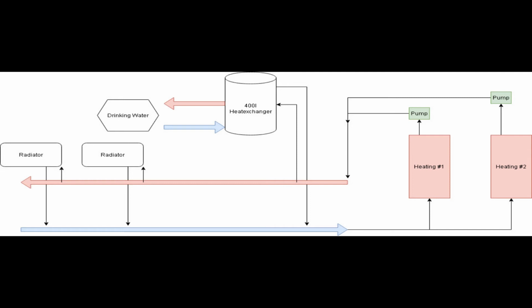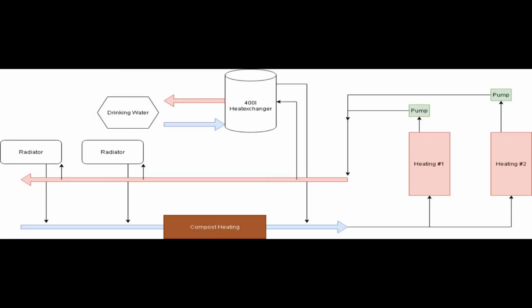The two main heat sources are set up parallel. The system is designed with the idea in mind that only one of the main heat sources will run at any time, never both. The integration of the compost heating into the system, however, will be in series. As you can see in the diagram, the compost heating will be installed in the backflow of the current system. This gives the option to run any of the two main heat sources should the compost heating not provide enough temperature. That concludes this video.